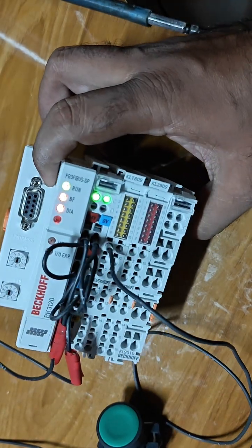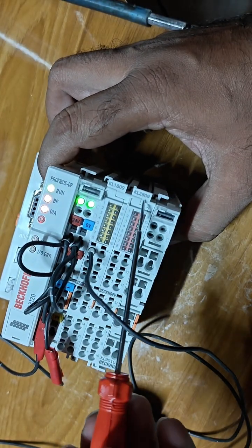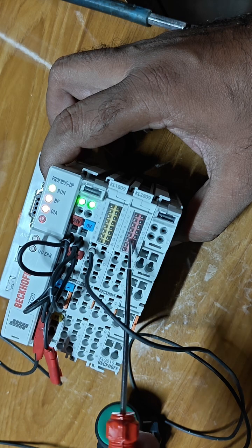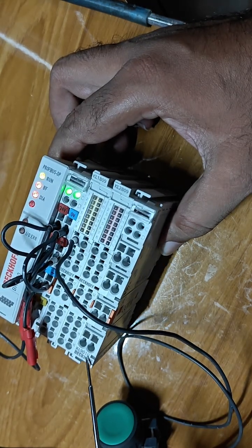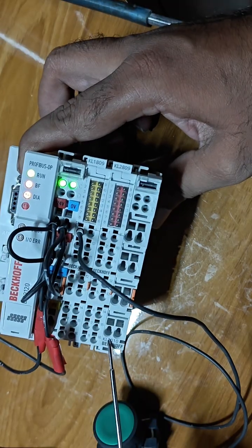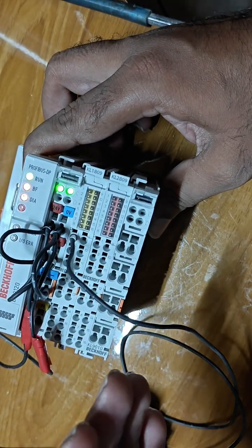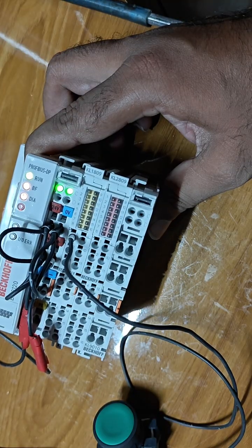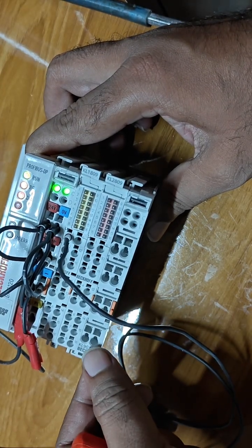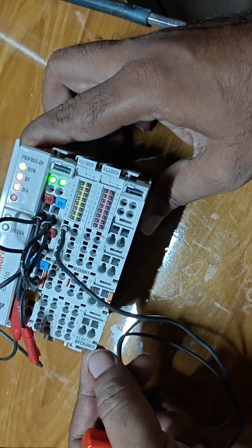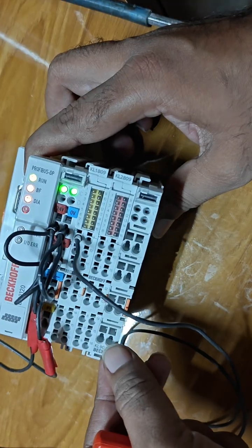Now I explain the most important thing. This is a KL2809. This is a 16-bit output, and the last one is a bus termination. This is a KL9010. Bus termination informs the system that this is my last module, and there are no more input or output addresses. So on every distributed IO we connect the KL9010 last. This is a distributed bus termination card.